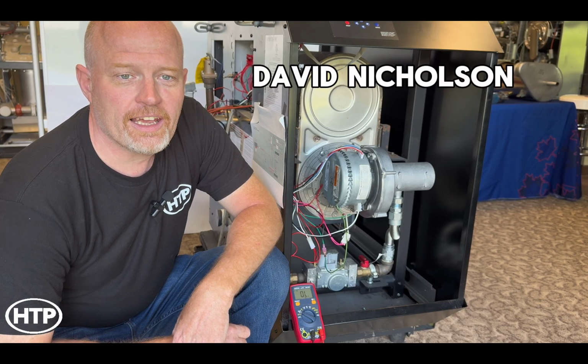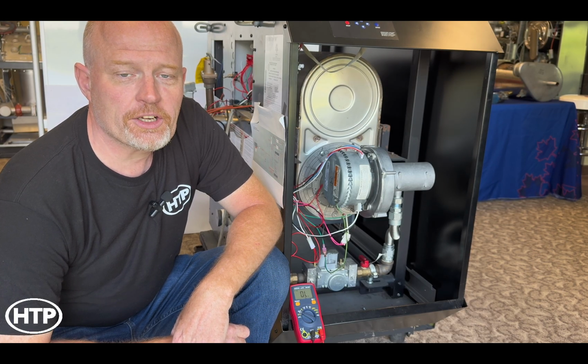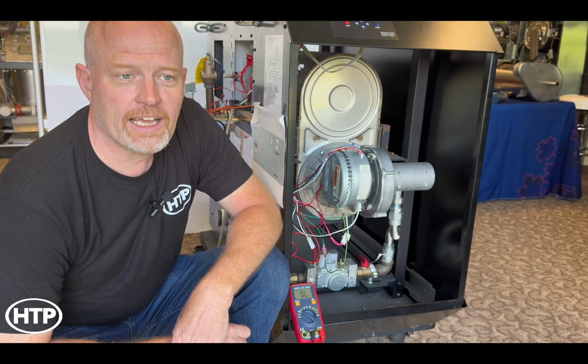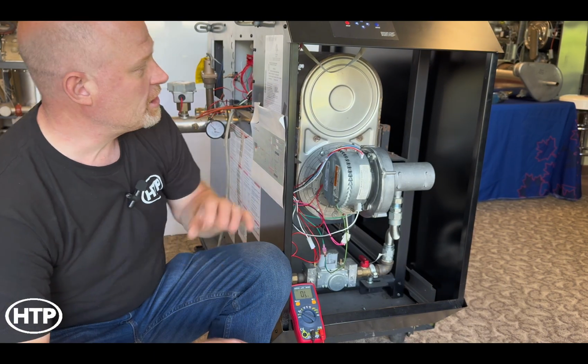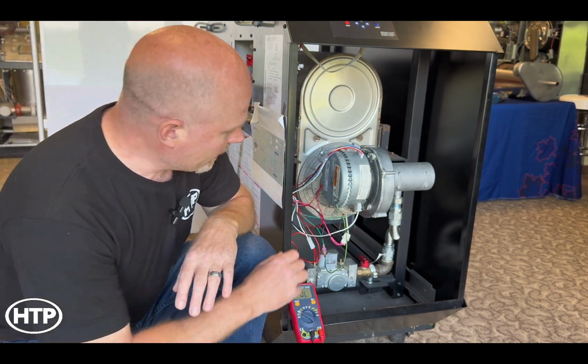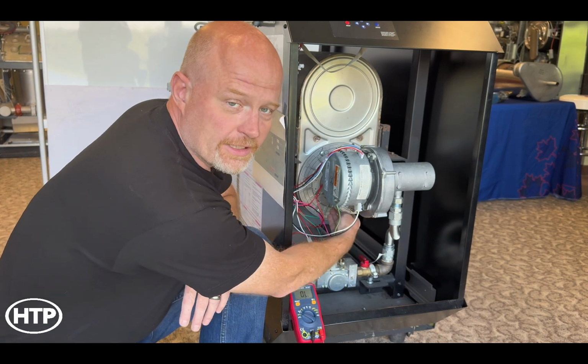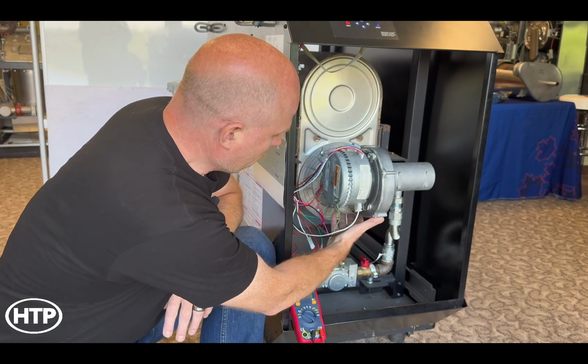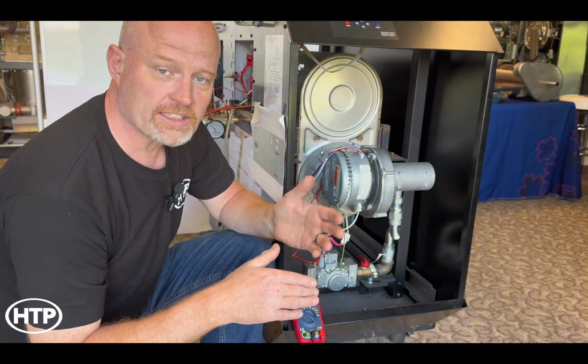Hi, this is Dave with HTP Tech Tips, and today we're going to go over an F15 and F16 on your HTP MODCON boiler. That error code is caused when the flapper that's located just on the other side of this blower here sticks open or sticks closed.